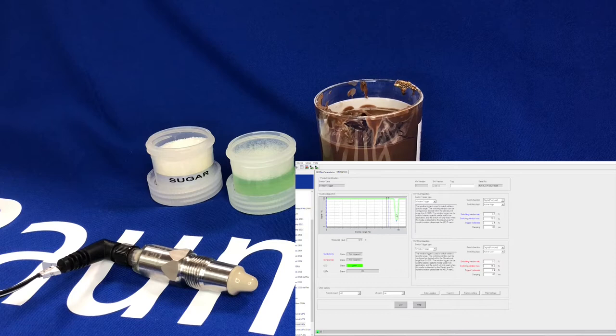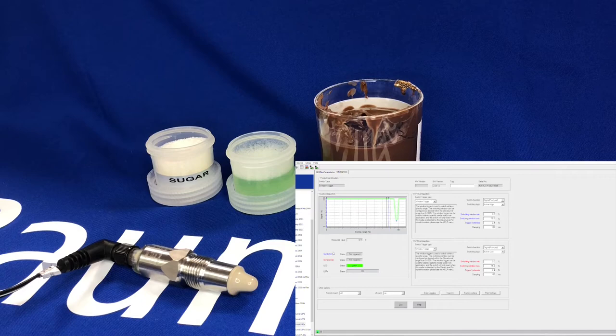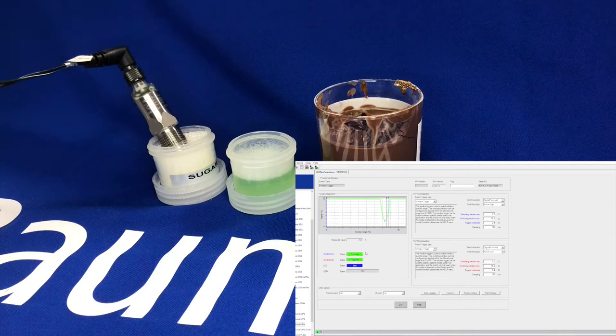The two trigger points are set at factory settings of 0 and 75.3%, so switch one and switch two are not triggered. If I introduce the sensor to some media such as sugar, you can see the green lines moved to within both windows.